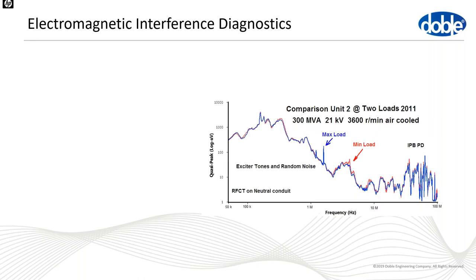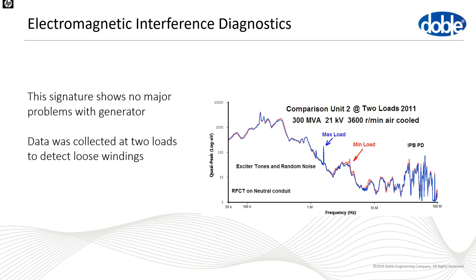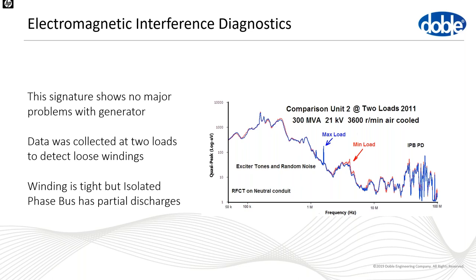Here's a case study example. For a generator with no major problems, we see excitation noise in the lower part of the spectrum and some indication of bus discharges at higher frequencies. Data was collected at two load levels to detect loose windings — an increase in stator current increases electromagnetic vibration, which raises ambient EMI levels. A significant difference between the two loads indicates windings becoming loose in the slots. In this case, the winding was tight, but there was some discharge in the bus system.